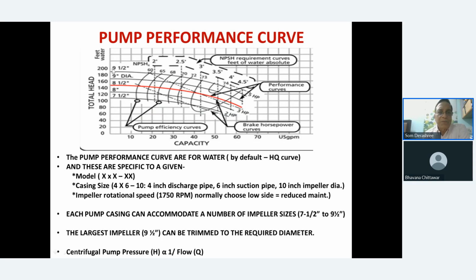So the largest impeller that you can accommodate in this particular pump is 9.5. And the minimum size that you can accommodate in this particular pump is 7.5. So within this range you can operate, and always try to select somewhere in between, so that in case you need a little higher head and higher flows, you can go impeller up, and you can go impeller down. Try to select as high a one as possible because that gives you flexibility. Higher ones can be trimmed; you can even turn the diameter down in your workshop, maybe reduce it by half inches, so 9.5 can be made into 9. So that is possible.